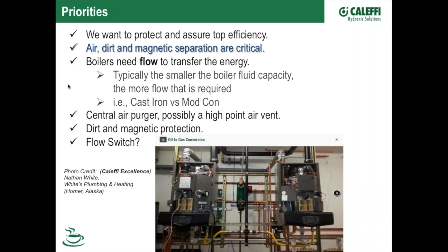So I would say those are probably the key and the most important on the boiler installation: the air, dirt, and possibly magnetic separation. Things have changed in the way the boilers are made. We've got to really pay attention to that. We've got to make sure that we've got good transfer between the flame, the 800-degree flame inside that heat exchanger, and the fluid that's circulating around through your system.